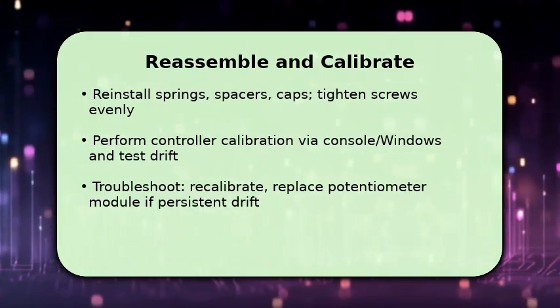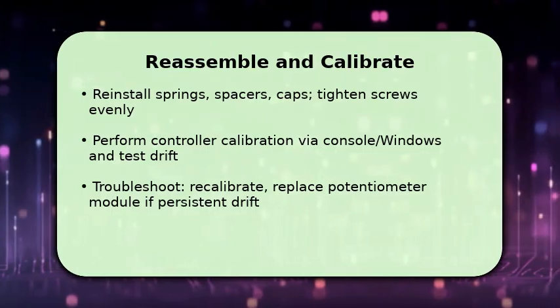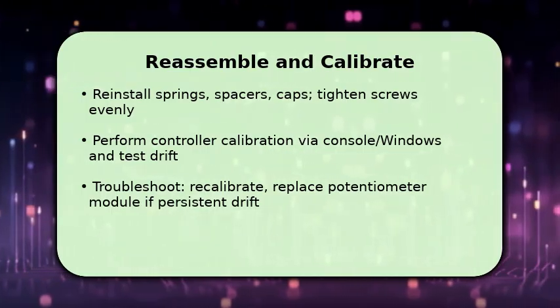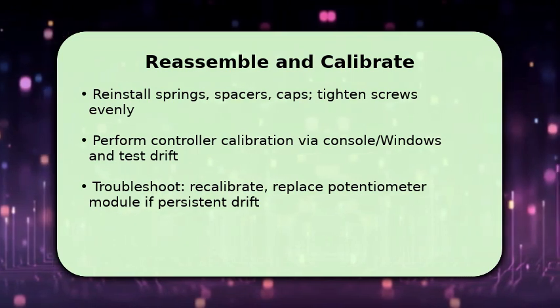If drift persists, you may need to replace the joystick potentiometer module. One key troubleshooting tip: if a stick reads off-center, recalibrate.